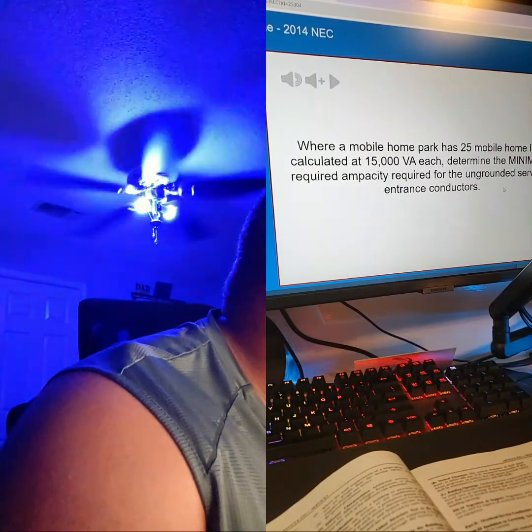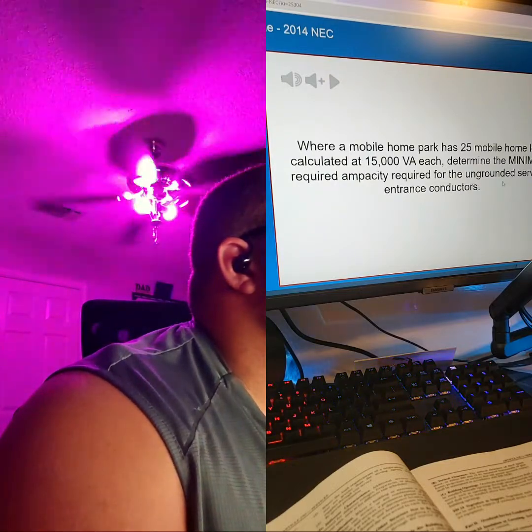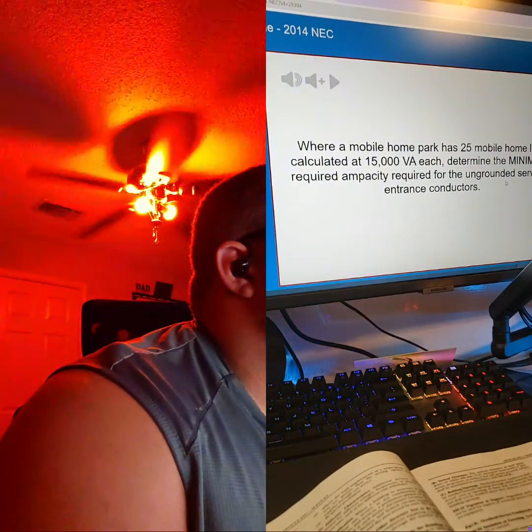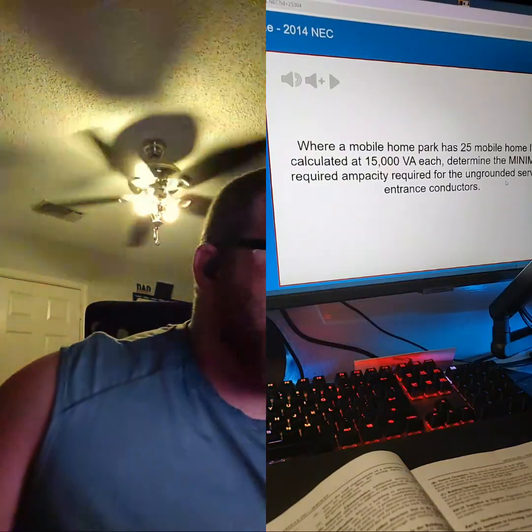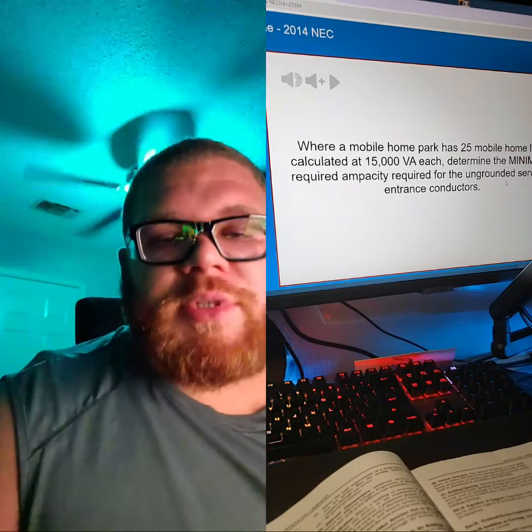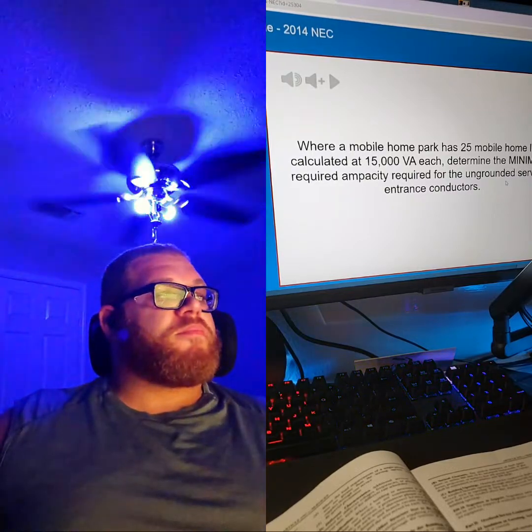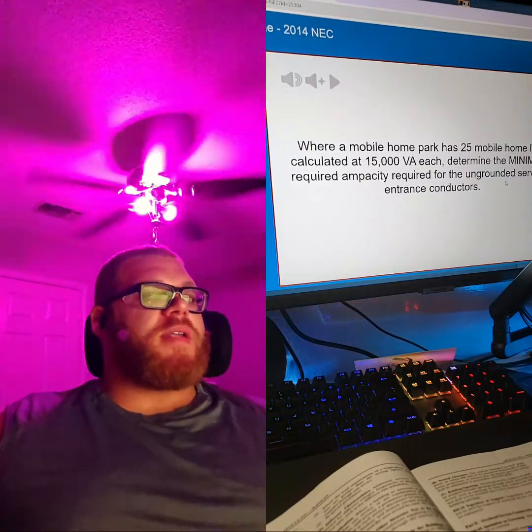Hold on, let me do a little math. Did you do 240 by 15,000? I divided 15,000 by 240. It gave me 62 point... I thought you said it was 62. 62.5, and then I just multiplied by 1.25 and got 78.125. So I say 80 amps.